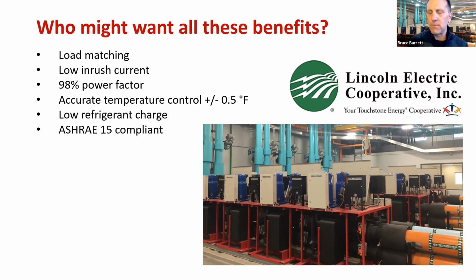The added bonuses here, very low refrigerant charge. Very quiet chiller. This mechanical room is large, but it's also very, very quiet. Really a great job for us. And we're controlling within a ½ degree on the heating and cooling side for this job. If you ever get over to Lincoln, he's very proud to show off his facility. We're proud of it as well. It was the very first geothermal heater chiller we did with true variable speed compressors.